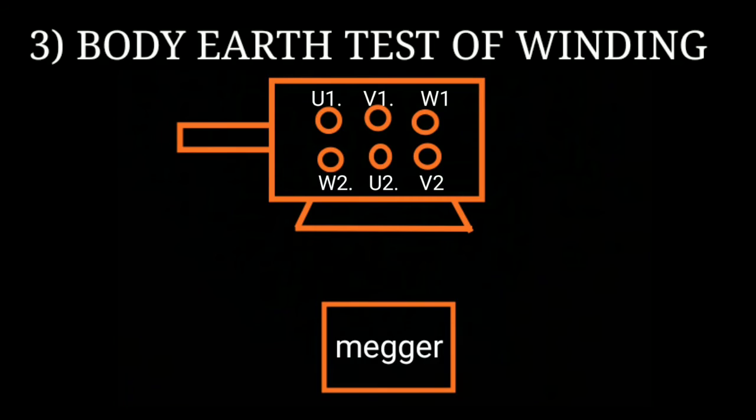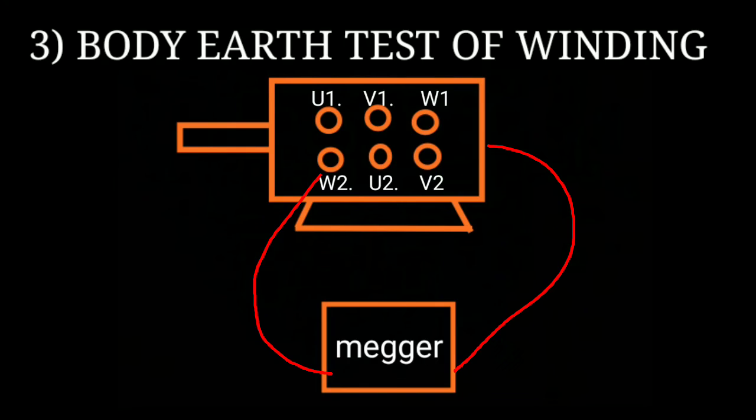Our third test is the motor winding body earth test, performed between winding and the body of the motor. Your megger probes are connected between the winding and the body. If the meter reading shows zero ohms, that means the motor winding is body earthed. If the meter reading is infinite, it means the motor winding is okay.